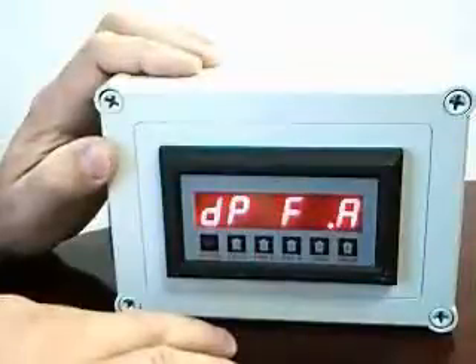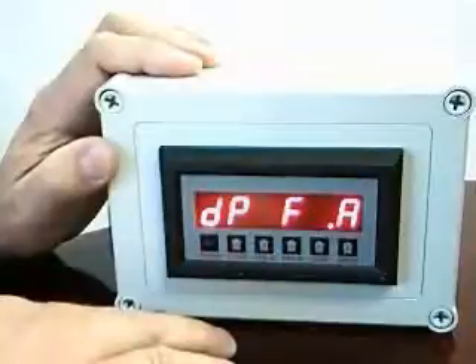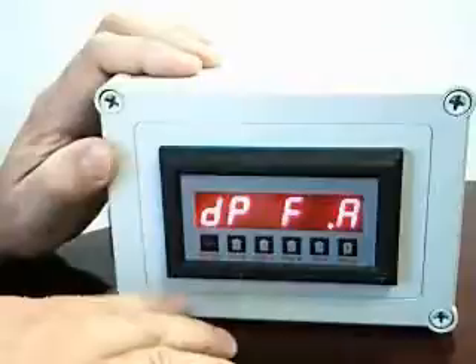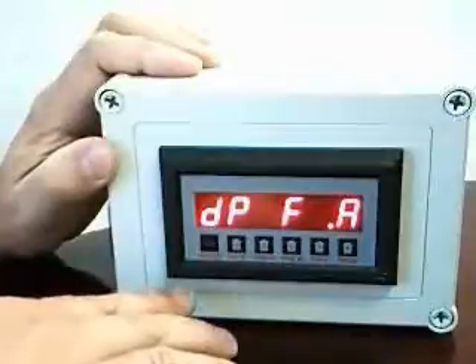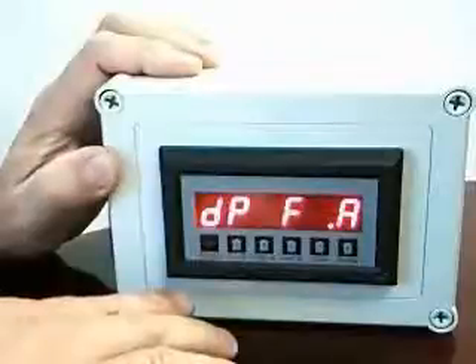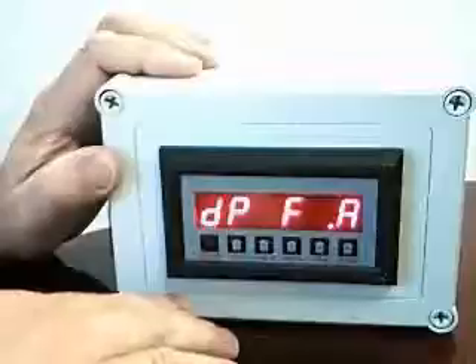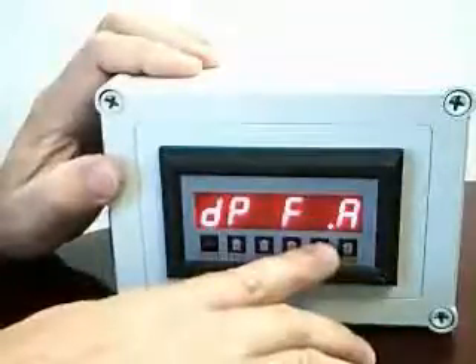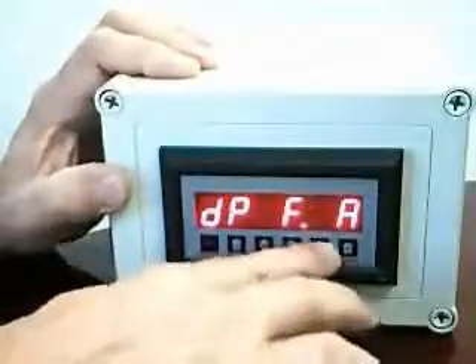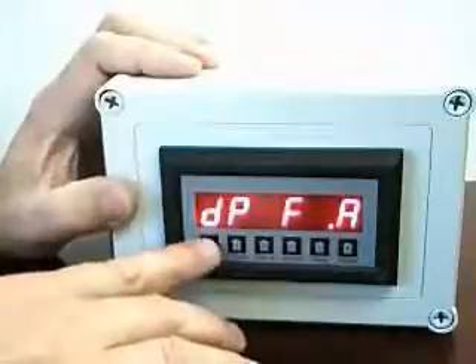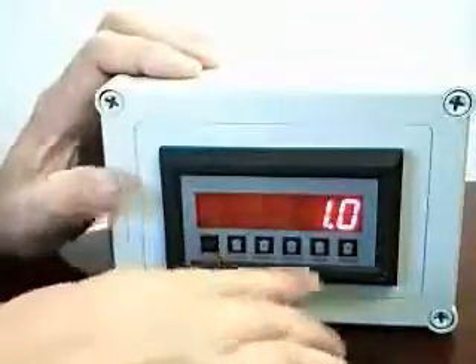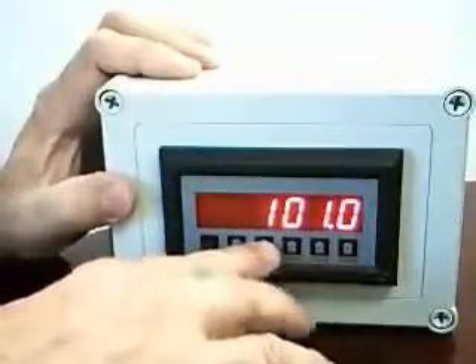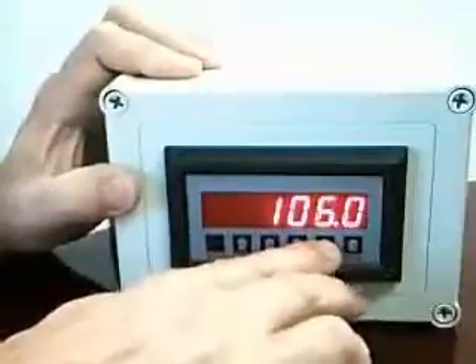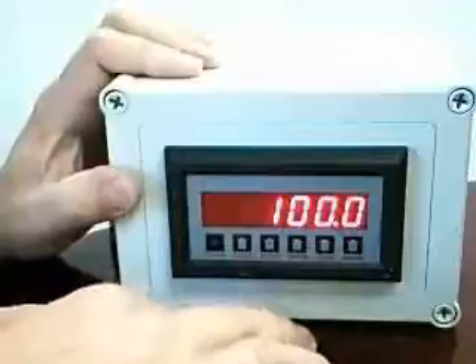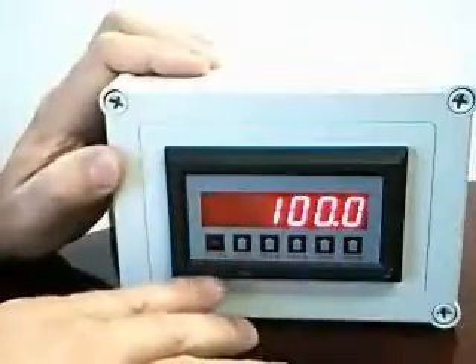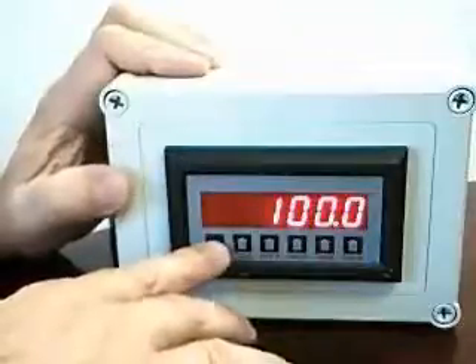These abbreviations on the display are meant to provide a prompt for you. In this case, it's showing the decimal point that's going to be used for the factor for the A channel. And I'm going to be entering this with a resolution down to tenths of gallons on my KFactor. So therefore I'm going to choose a decimal point position that will give me that amount of resolution. After pressing this, I can now go through and enter my 100 pulses per gallon KFactor with a resolution of 4 digits for this example. Once I have the desired number appearing, I can hit Enter to move to the next channel.